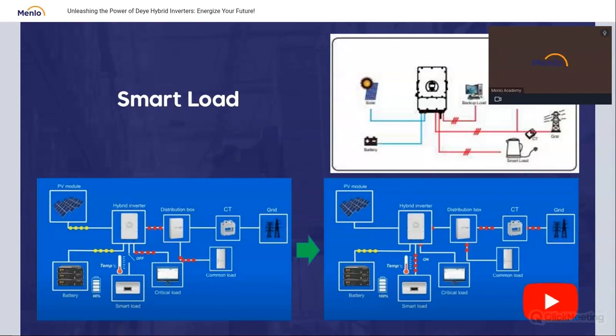The second solution is: if you set it with proper settings, it doesn't take energy from the grid to support the smart load output, never ever. So you only start to support this device with energy when you have too much energy that you're supposed to send to the grid. Never charge this device from the grid—you need to never buy energy from the grid to support that smart load output.